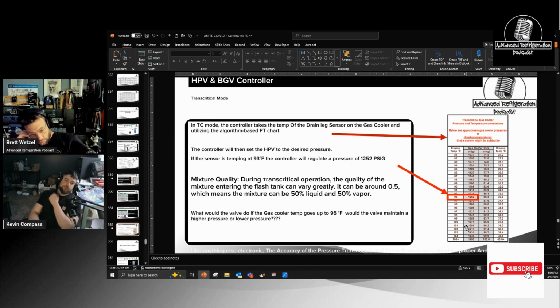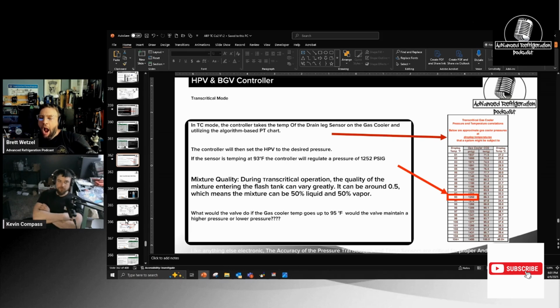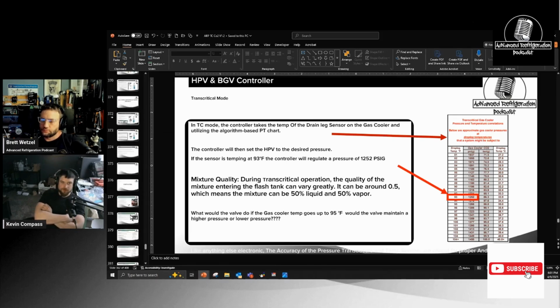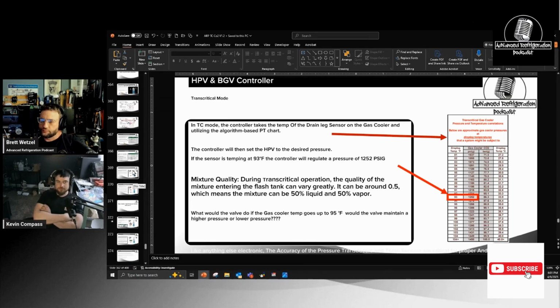Yep. It happens a lot. It happens more with the sensors mounted on the outlet of the gas cooler than it does inside the rack, because usually the rack is shaded and a little cooler. I don't care how much Armaflex you put on there, they all do it when they're down long enough. So generally what I'll do is take duster, flip it over and spray it in there and let it cool down just to get the rack back started, especially if it's been down for a while, and it'll take back off. Cool. Anything else you want to talk about?